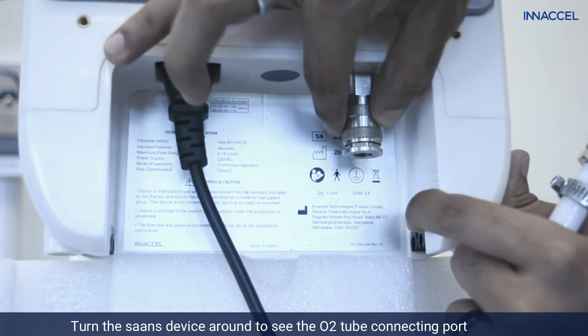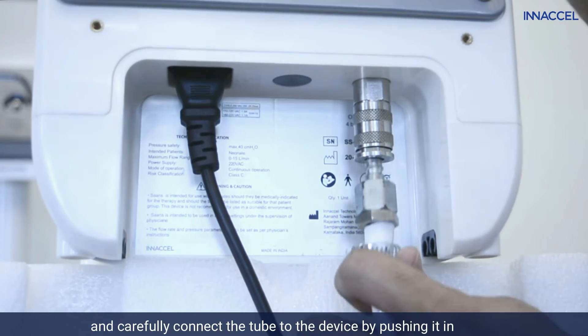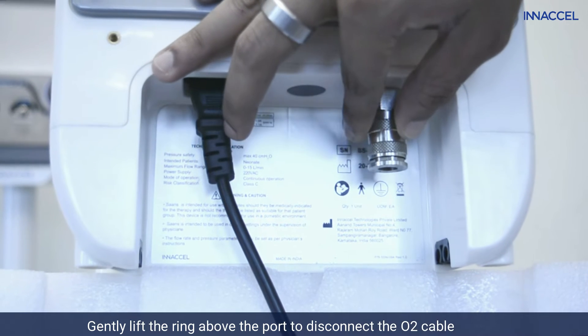Turn the Saans device around to see the oxygen tube connecting port and carefully connect the tube to the device by pushing it in. Gently lift the ring above the port to disconnect the oxygen cable.